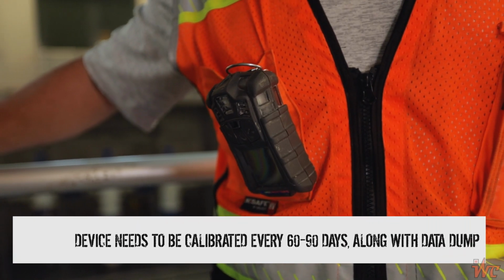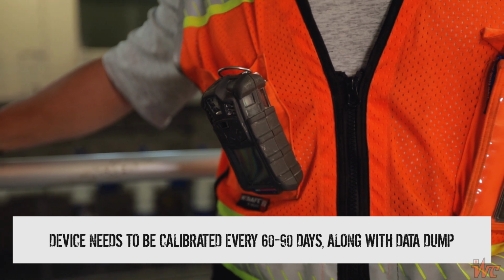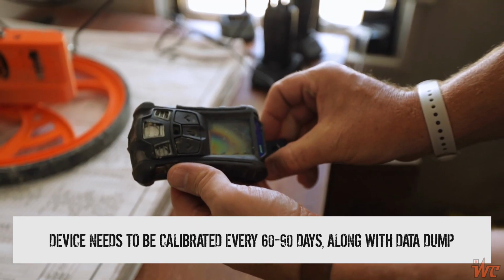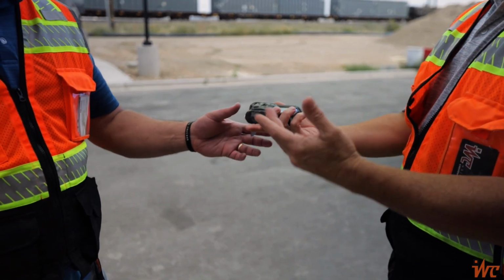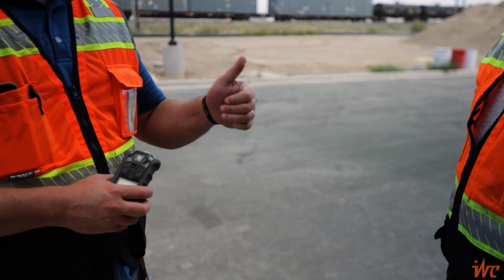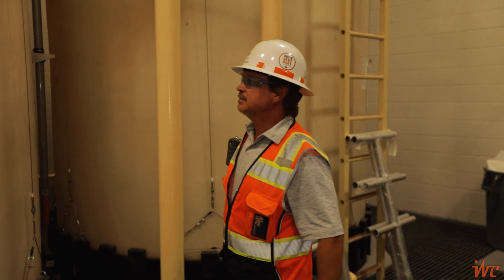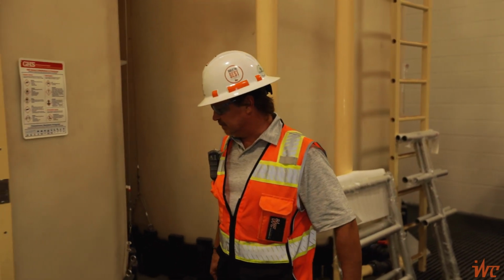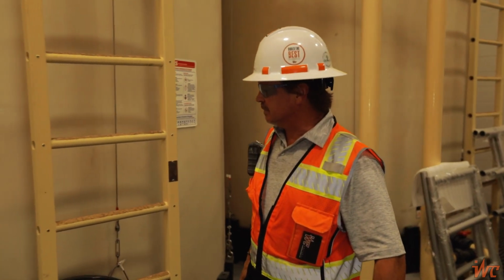Finally, the Altair 4XR needs to be calibrated every 60 to 90 days, along with a data dump at the Brigham City office. It is the foreman's job to ensure that the gas monitors have been correctly calibrated. Proper calibration ensures that the gas monitor will be functioning properly during use, keeping everyone safe.